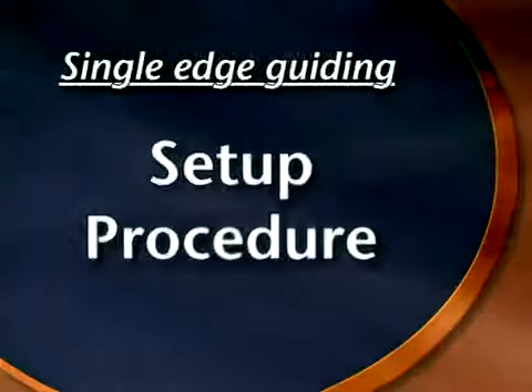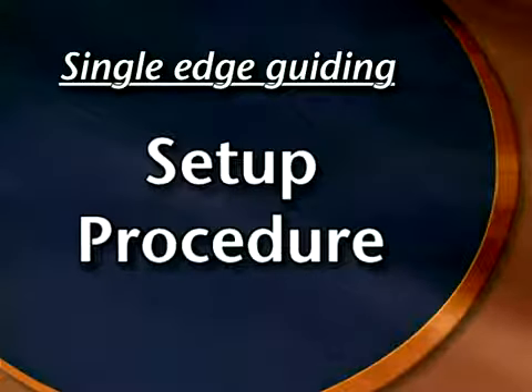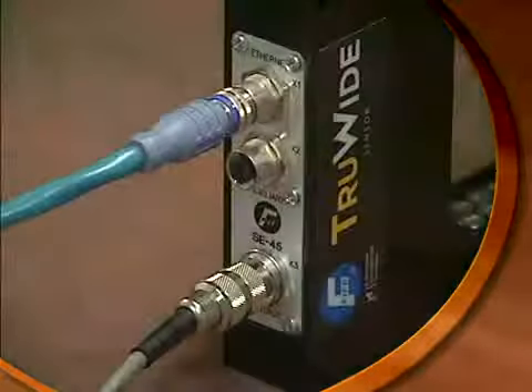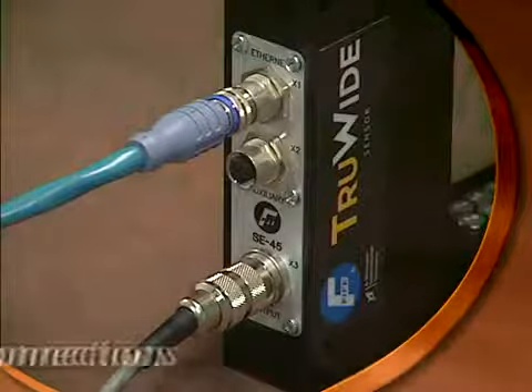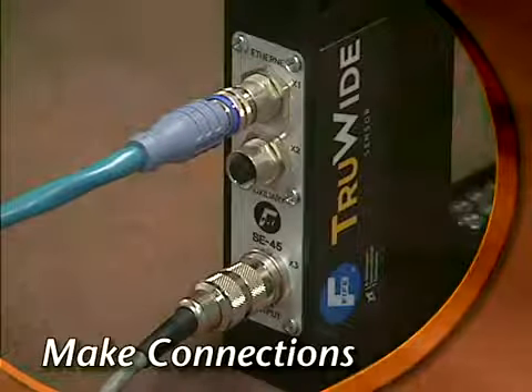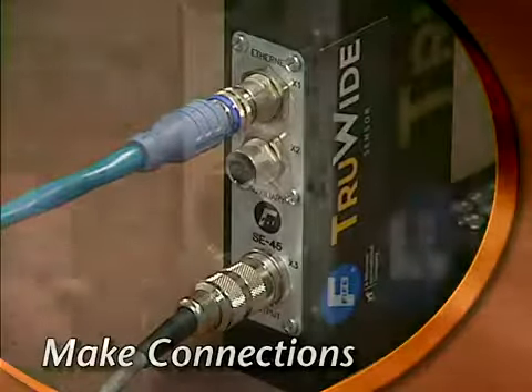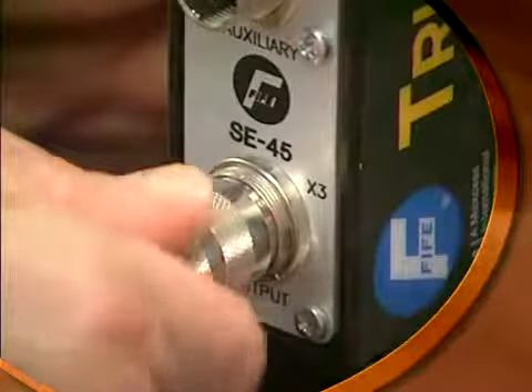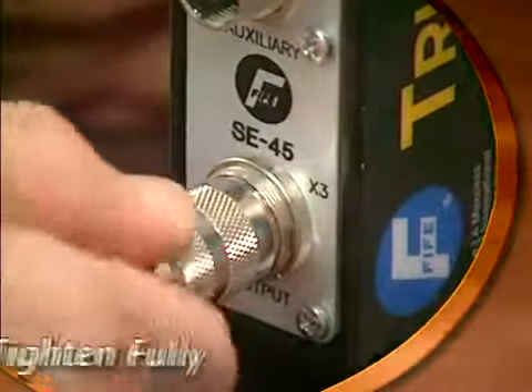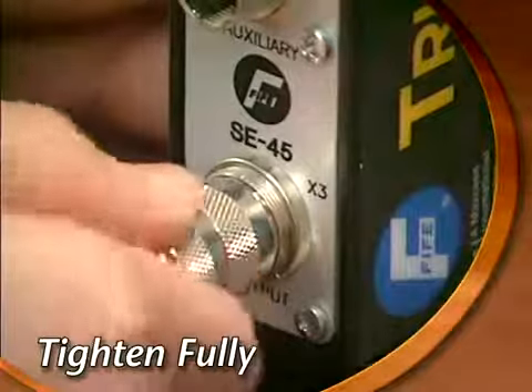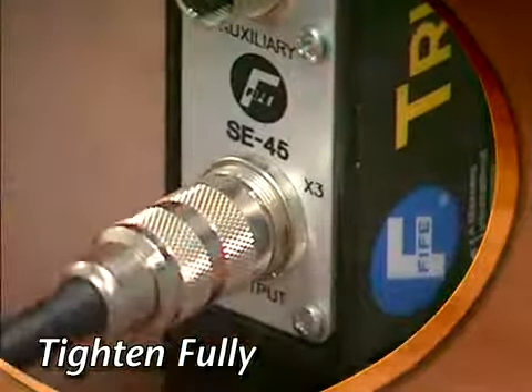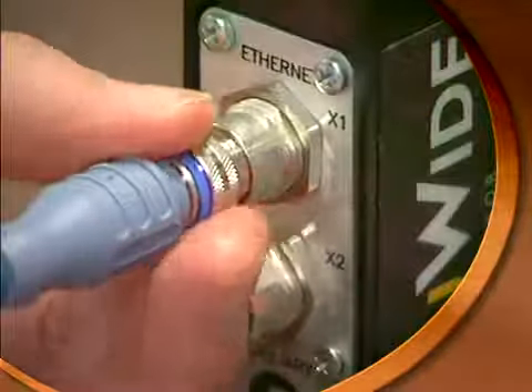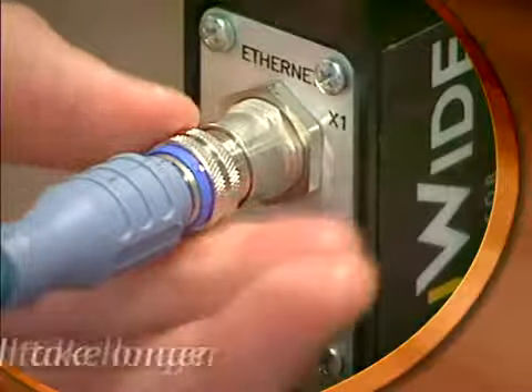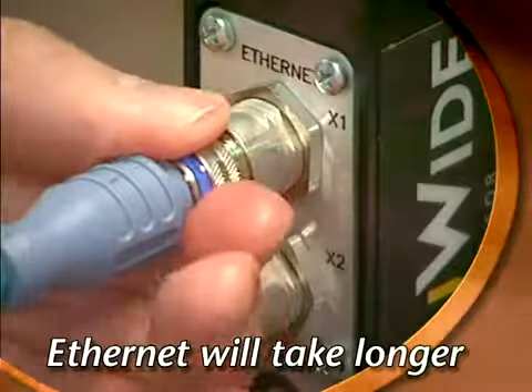To learn the edge location, perform the following steps. First, install the sensor by connecting the SE45 analog connector and then the Ethernet connector. Note, it's important to thread each connector all the way until it's tight, or your sensor may not operate properly. The Ethernet connector has more thread and will take longer to connect than the SE45 connector.